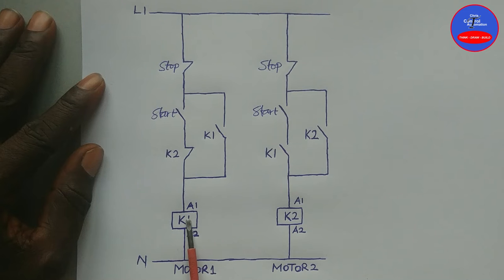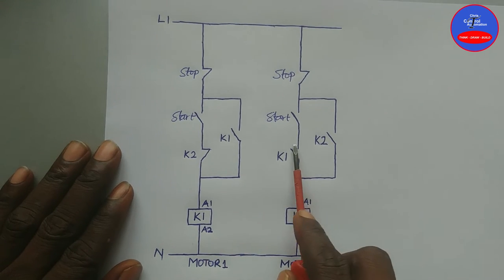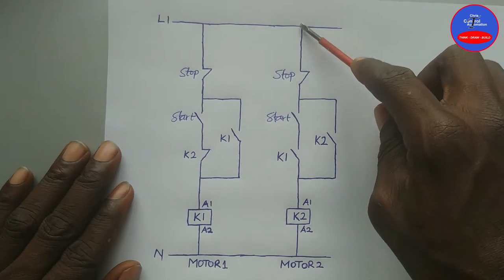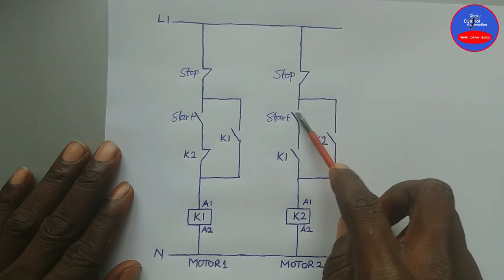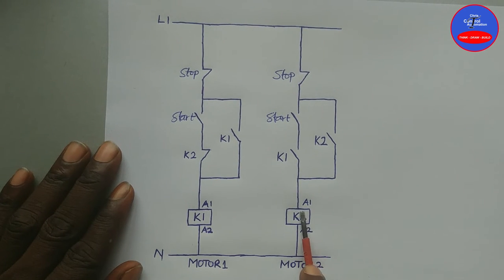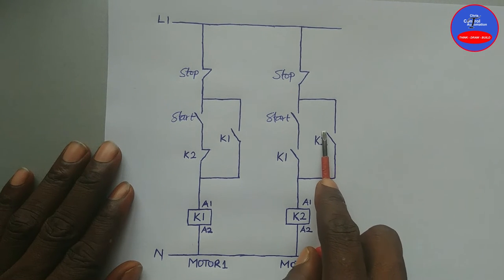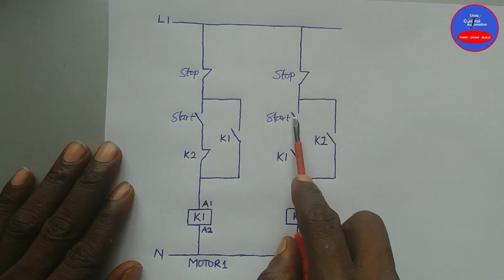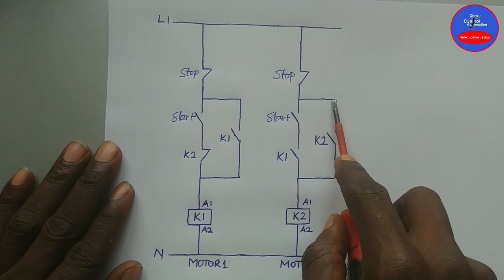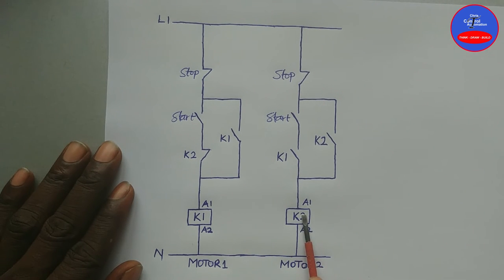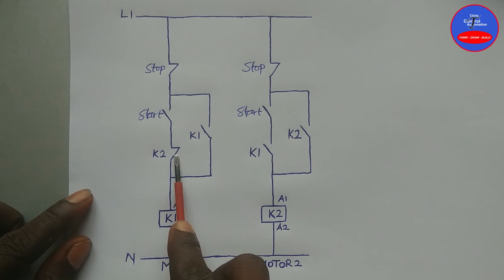As K1 is energized, this contact is closed. Therefore when you press on the start button, current can flow through this close contact, through this close contact, through this close contact, through this close contact on K1 to energize K2. The moment K2 energizes, this contact will close to provide a hold-on, so that when we remove our hand from the start button this contact will open, but current can still flow through this close contact on K2 to keep K2 in the energized state.